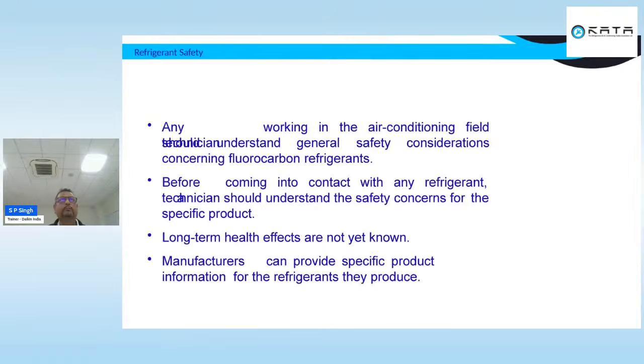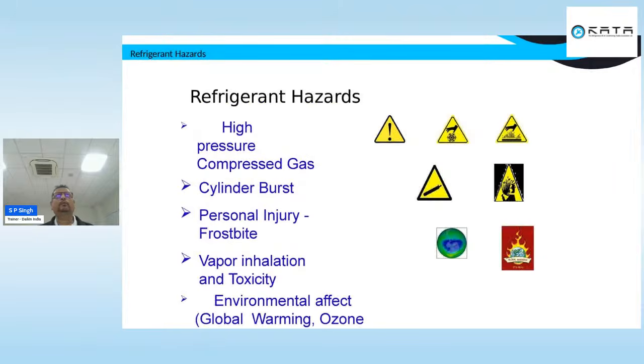Apart from that, the working air conditioning field technician should understand the general safety concerns before coming into contact with the refrigerant. We should know what can harm us if it directly comes in contact with us. The refrigerant hazards include high pressure causing cylinder burst.